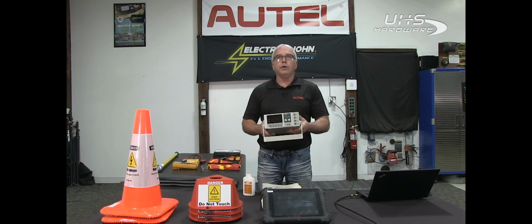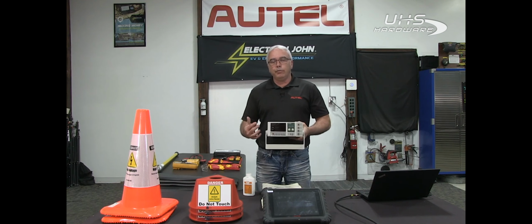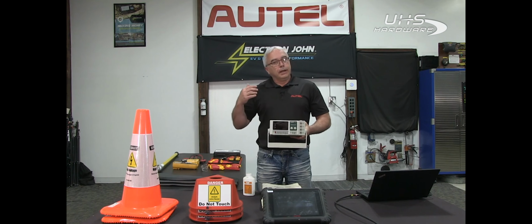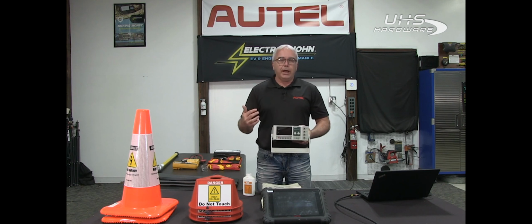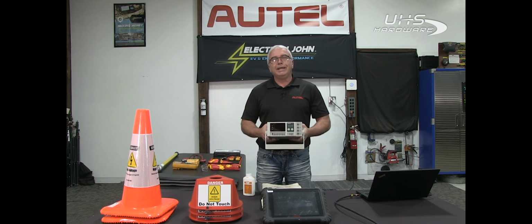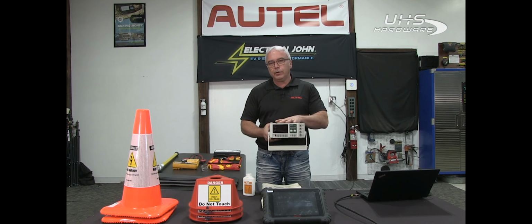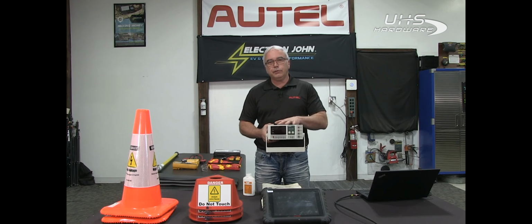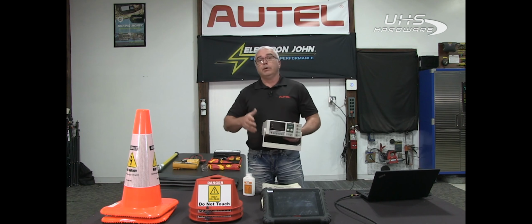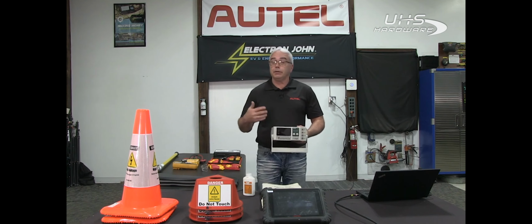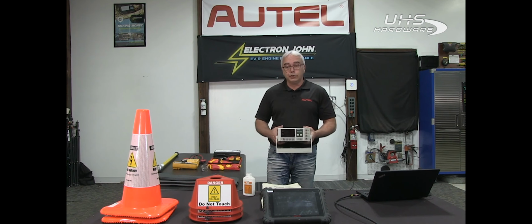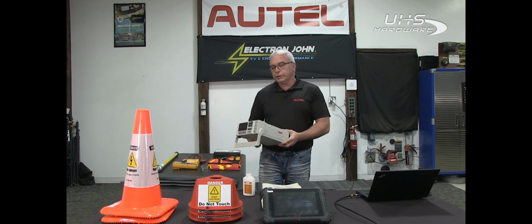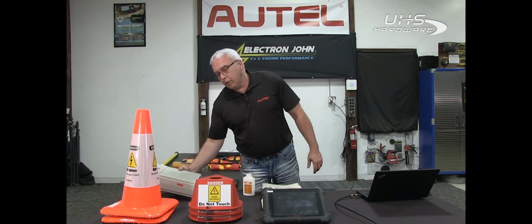We said before that we need a milliohm meter. Now, true, your regular digital voltmeter can read milliohms, but not down to the small, minute readings we need for testing stator windings. We covered stator winding testing in detail in part 2 of this 4-part series, so we definitely need a milliohm meter.